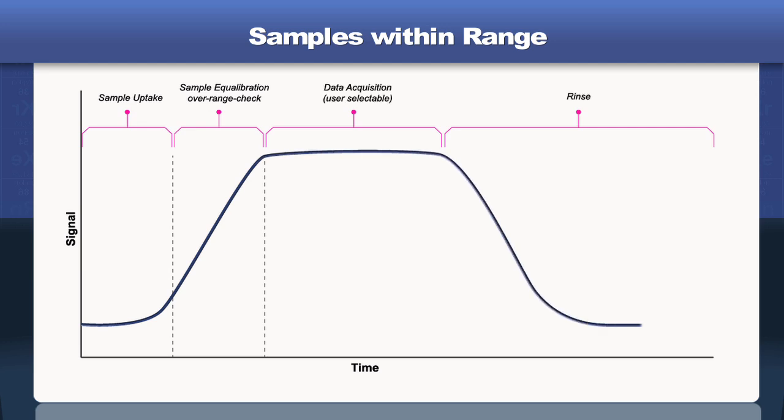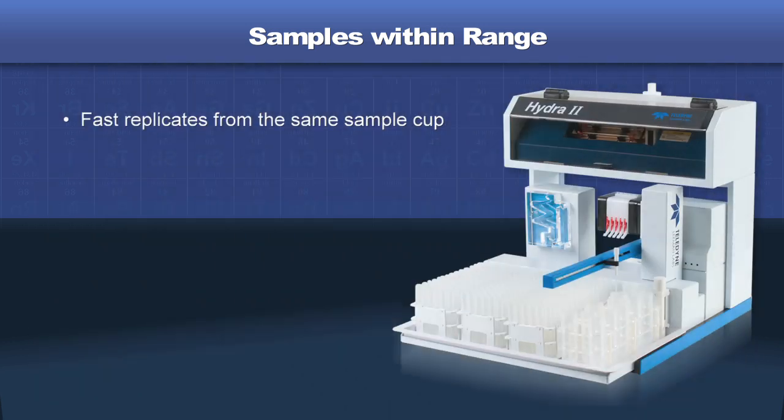The analysis cycle for a typical sample involves a short period of sample uptake, sample equilibration, data acquisition, and rinse. Unlike conventional systems that consume all of the material in the same cup, the Hydra 2 AA is able to quickly conduct multiple replicate analyses from the same sample cup. This approach ensures high measurement quality and allows the operator to reanalyze the sample if needed.